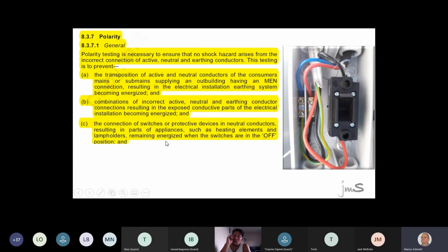Do we agree that phase is phase is phase, neutral is neutral, and earth is earth? If we swap phase and neutral around on an appliance, can the kettle still work? Absolutely. But which conductor do we switch on and off? The phase or the neutral now? Neutral. So if I switch a neutral off, do you agree that the inside of the kettle is still live? Absolutely. So small things like that.